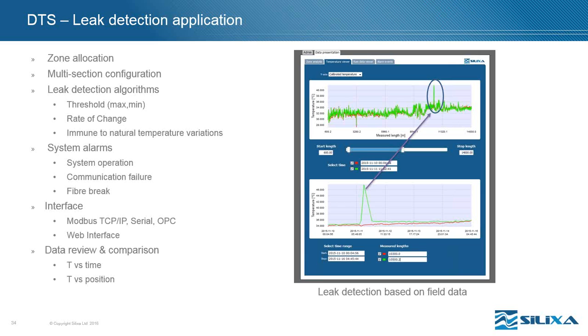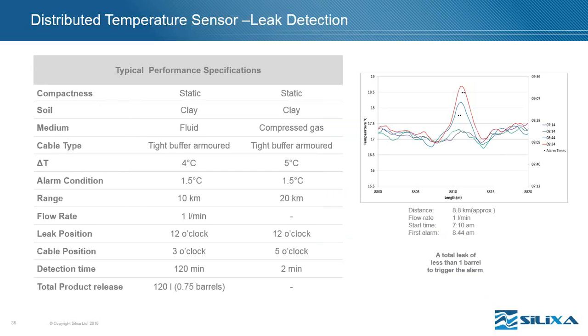We use a number of different leak detection algorithms, depending on the location. We have system alarms based on the operation, on the communication, also the fiber break, and we can build different interface modules to connect to the SCADA system. This is a typical performance for the distributed temperature sensor. Again, there are many different performances.